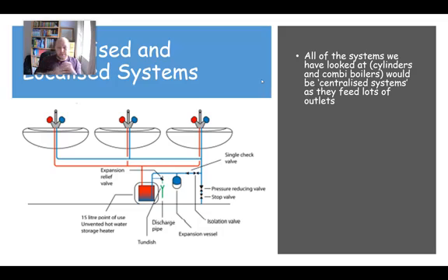For example, they need to run off a lot of cold water that's cooled inside the pipe before that water starts to run warm. Another issue with that, apart from the wastage of water, is also there's a risk of Legionella. Because that water has cooled inside the pipe, it's going to drop out of the safe zone, which is above 40 degrees ideally. It pasteurizes at 60, and it goes into a zone where potentially there's a risk of Legionella bacteria growing, and if that happens, then obviously people are at risk from the water in the system.